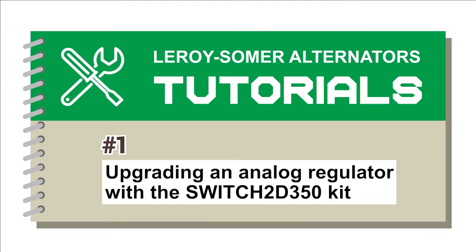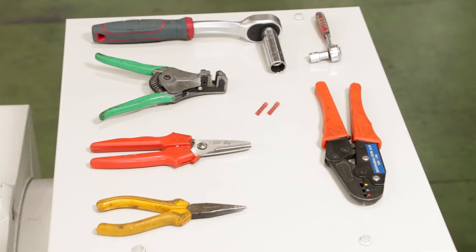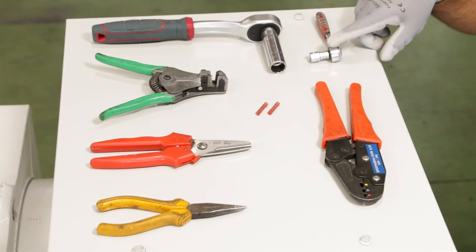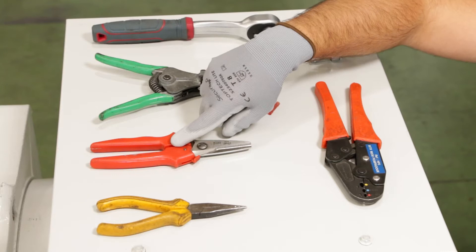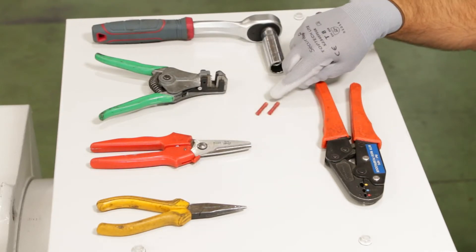Thanks to SWITCH2D350, it is very easy to replace an analog regulator with the digital D350 AVR. To do this, you need the following tools: a crimper, a 10 mm wrench, a 13 mm wrench, stripping pliers, cutting pliers, flat nose pliers, and two connectors.